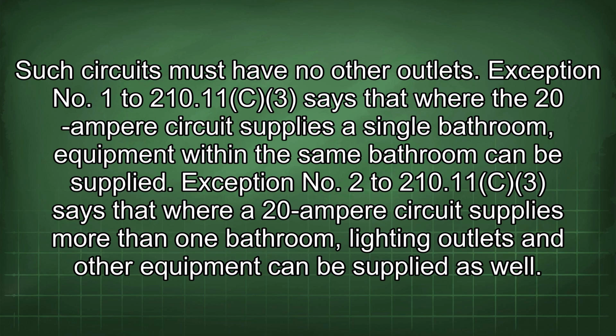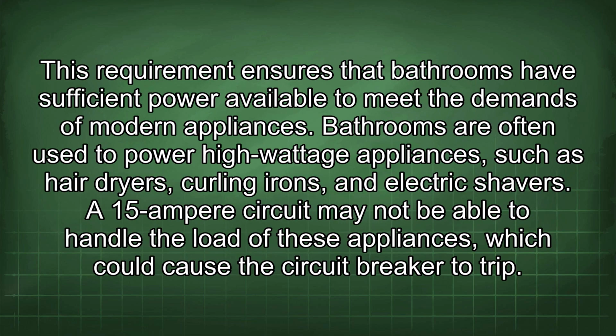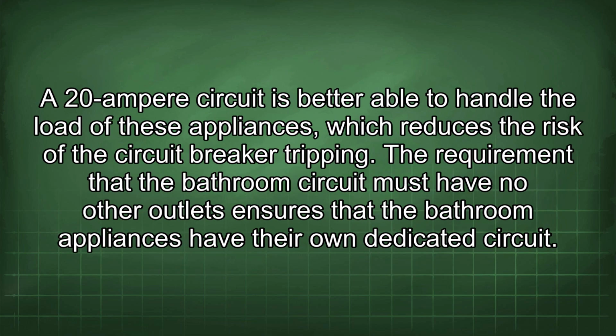Exception No. 2 to 210.11c3 says that where a 20 ampere circuit supplies more than one bathroom, lighting outlets and other equipment can be supplied as well. This requirement ensures that bathrooms have sufficient power available to meet the demands of modern appliances. Bathrooms are often used to power high wattage appliances, such as hair dryers, curling irons, and electric shavers. A 15 ampere circuit may not be able to handle the load of these appliances, which could cause the circuit breaker to trip. A 20 ampere circuit is better able to handle the load of these appliances, which reduces the risk of the circuit breaker tripping.